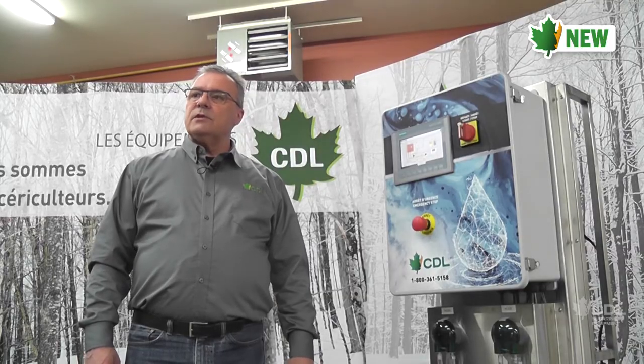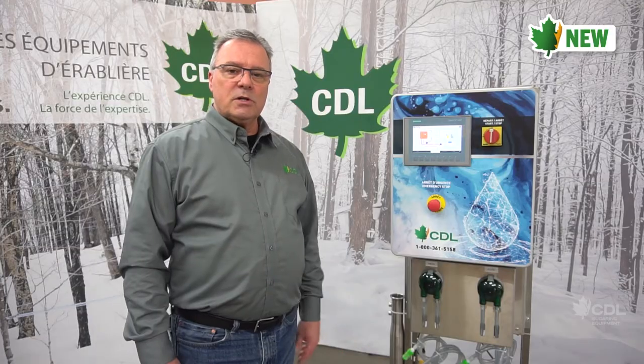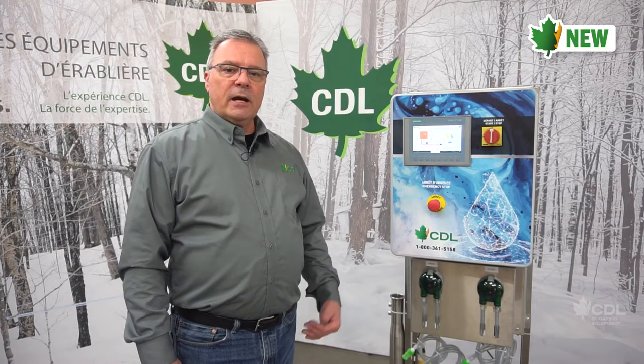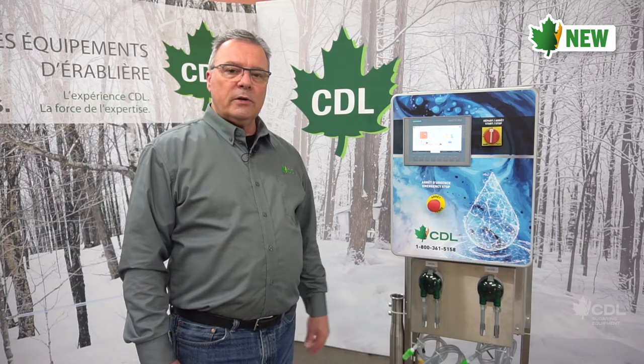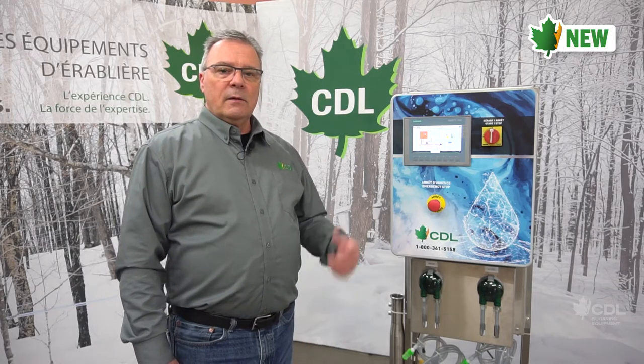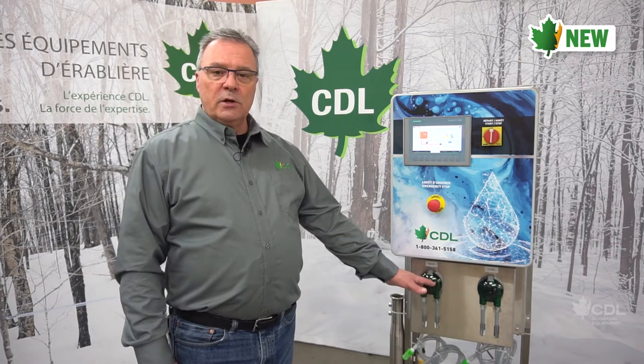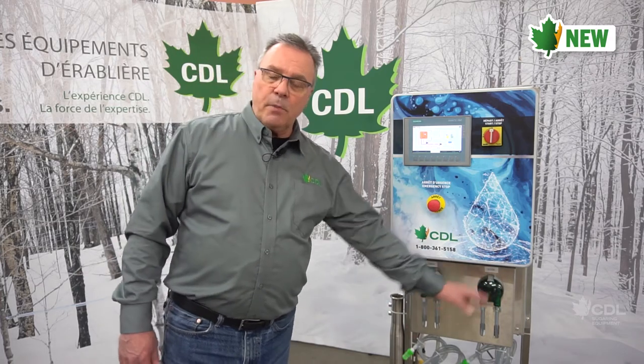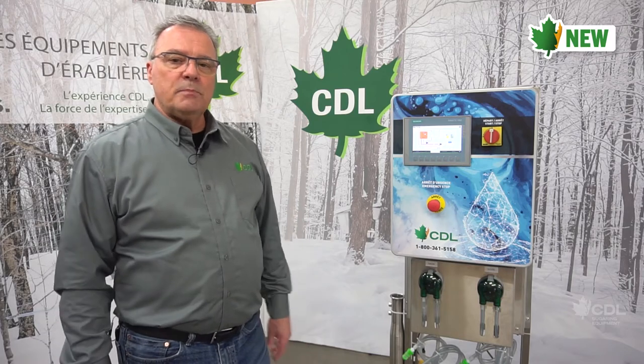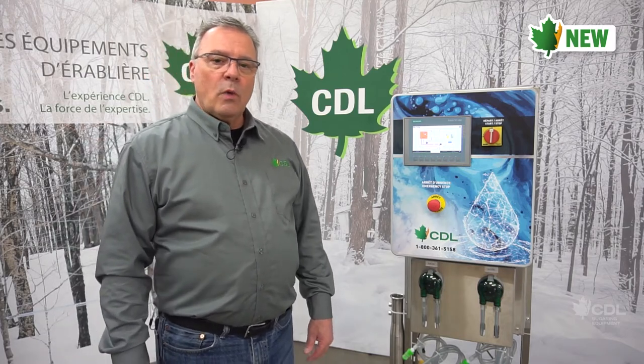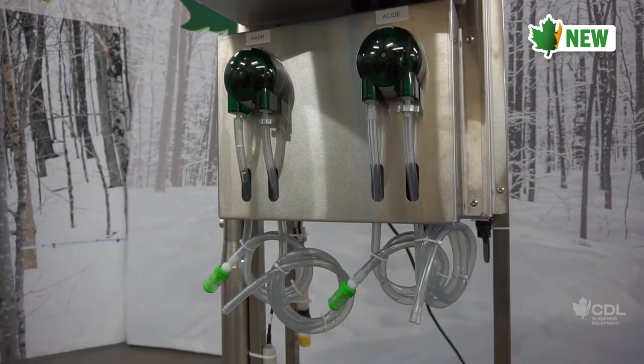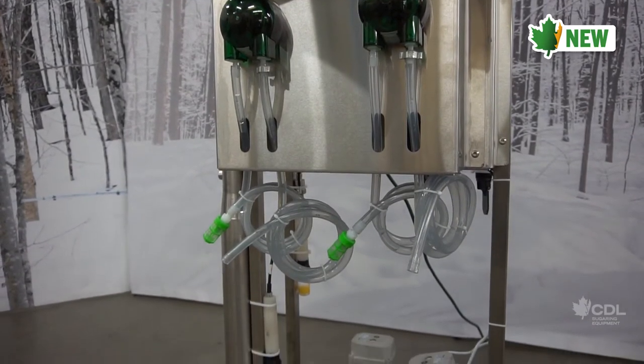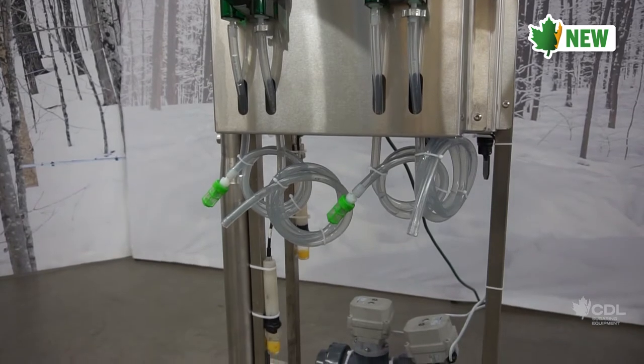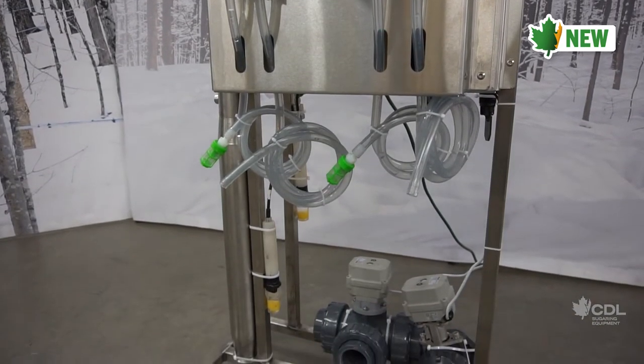Every water that does not comply with the regulation, a 6.5 to 9.5 pH, will have to be directed towards a neutralization tank. There, in this tank, you have another pH probe that will allow either pump, either the citric acid pump or the caustic pump, to function to neutralize the pH of the solution. Once that solution is being neutralized and the level of the tank allows it, then it will be flushed towards the dispersion field or to the dispersion tank as authorized.